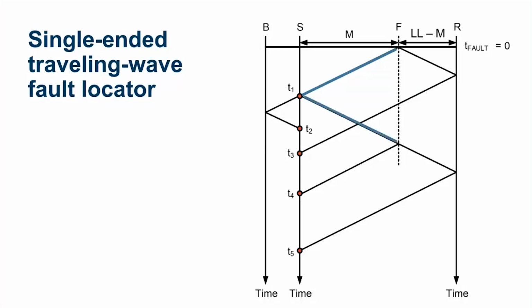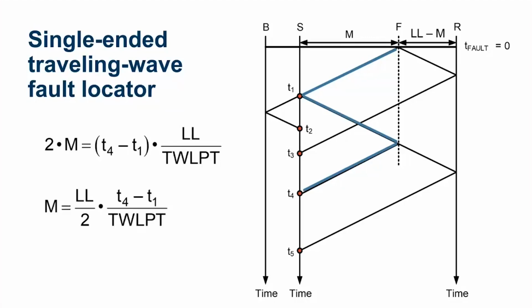This is going to reflect to our fault point here. And then when it reaches the fault, it's going to reflect back to our terminal. So we can use this information to calculate the fault point using the single-ended method. So we calculate 2 times M to be equal to time 4 minus time 1 times the line length over the traveling wave line propagation time. And then we just solve for M by dividing both sides by 2.